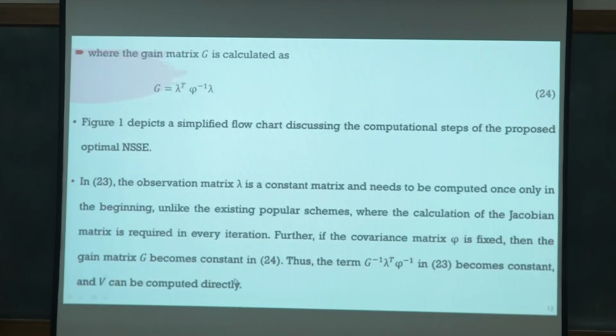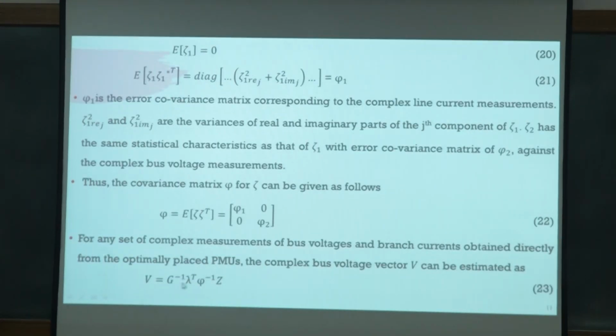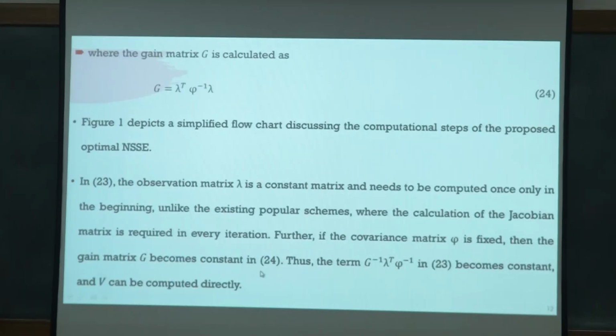G is designated as the gain matrix, calculated as lambda transpose times phi inverse times lambda, where lambda is the known observation matrix and phi is the known overall error covariance matrix, so G can be computed directly. Once we know G, we take G inverse, multiply by the observation matrix transpose and the covariance matrix inverse, with Z as the known measurement vector. So from this equation we directly find the complex voltage V without any iteration, using the optimally placed PMUs. That's why it is an optimal solution.